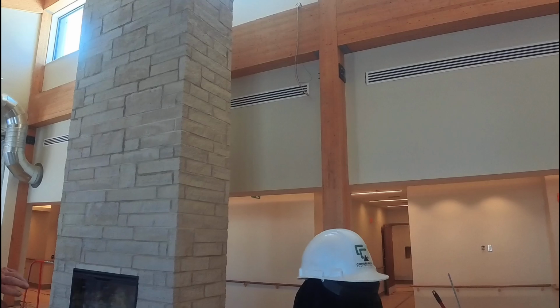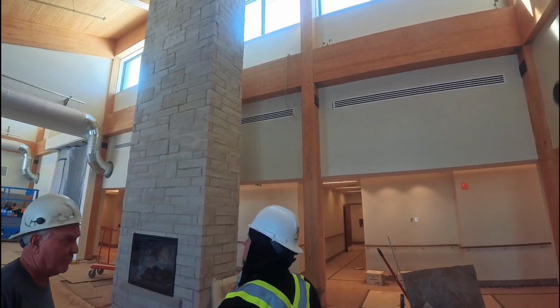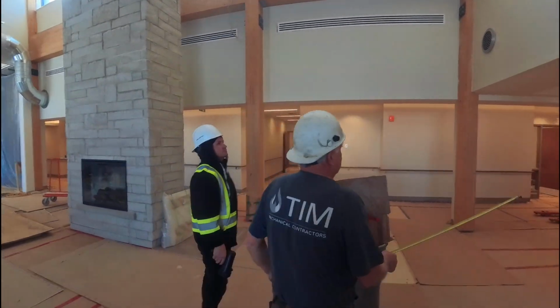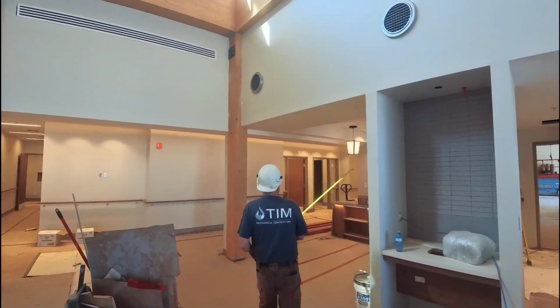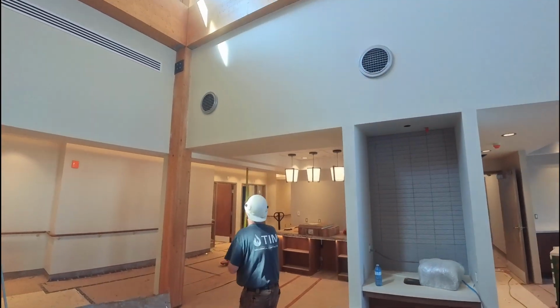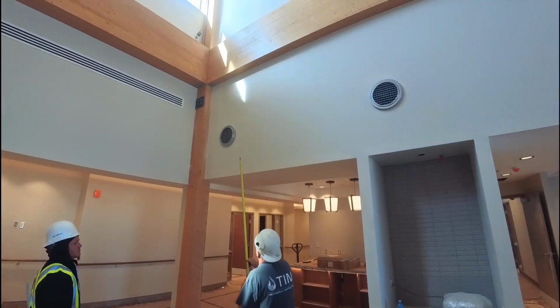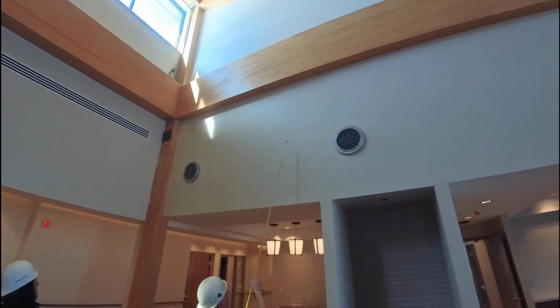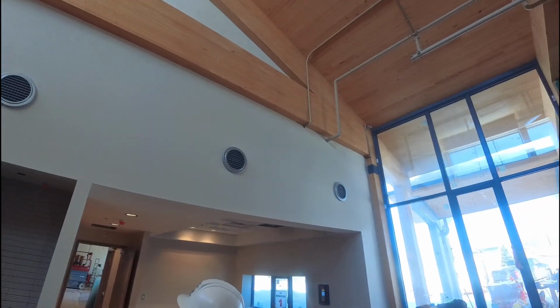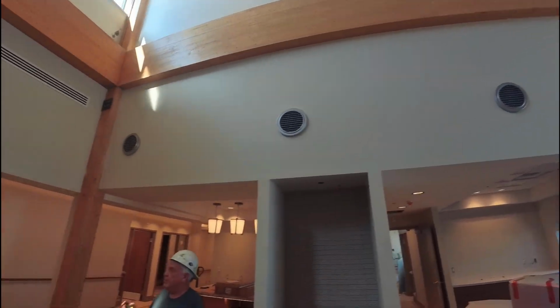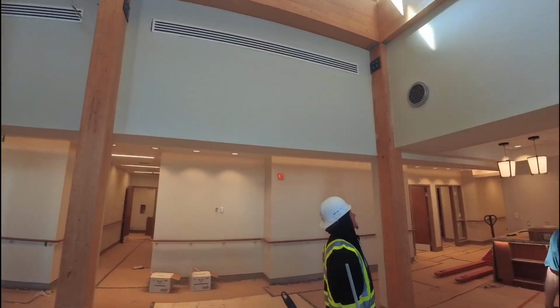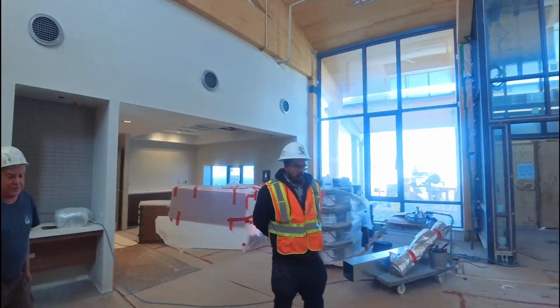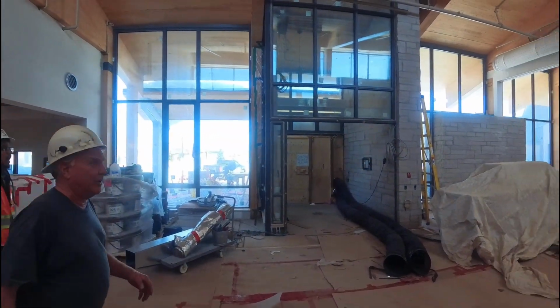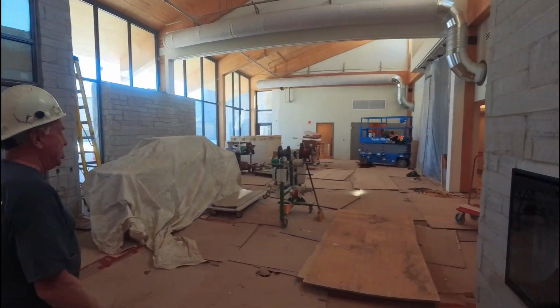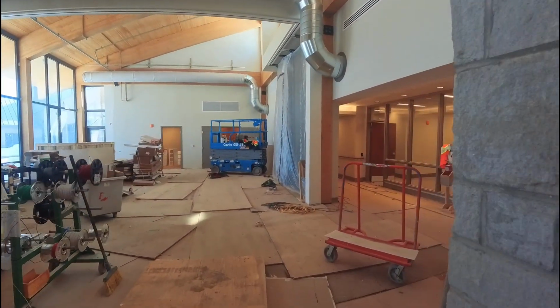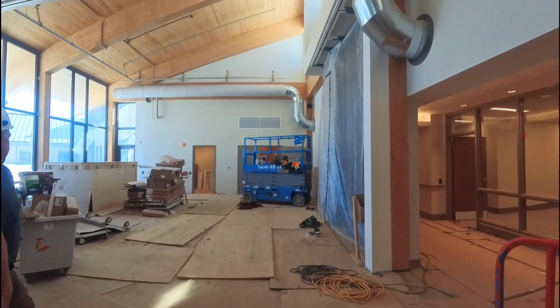this entire big area. The other supply of air for this room is off another 12-inch neck VAV. The duct runs in this bulkhead here, and it has four diffusers supplying air for this also large room. So you have three. That's the supply. That's the return. Down in the end, we also have a secondary return, and we have an exhaust.